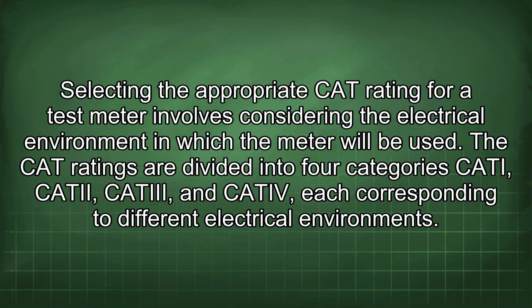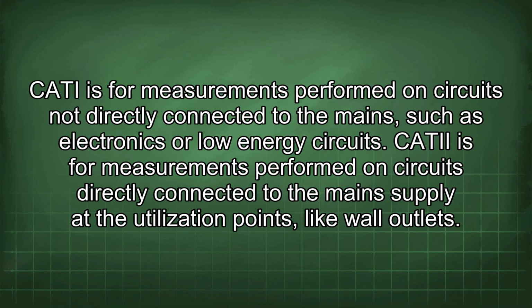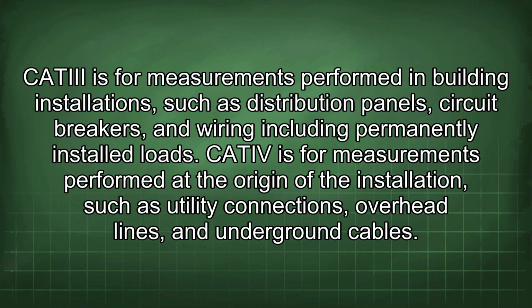Selecting the appropriate CAT rating for a test meter involves considering the electrical environment in which the meter will be used. The CAT ratings are divided into 4 categories: CAT I, CAT II, CAT III, and CAT IV, each corresponding to different electrical environments. CAT I is for measurements performed on circuits not directly connected to the mains, such as electronics or low-energy circuits. CAT II is for measurements performed on circuits directly connected to the mains supply at the utilization points, like wall outlets. CAT III is for measurements performed in building installations such as distribution panels, circuit breakers, and wiring, including permanently installed loads.